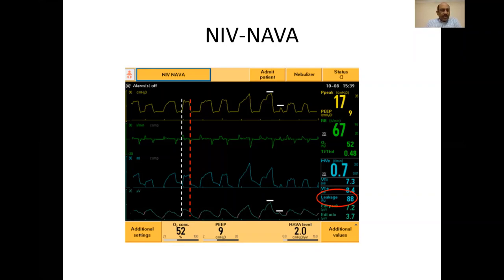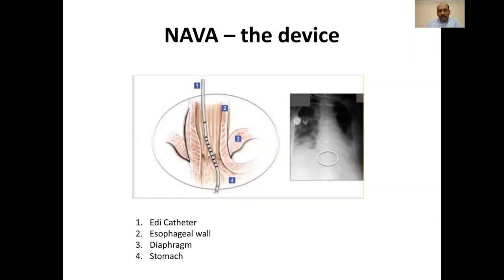By the way, NAVA can also be delivered invasively. The device is an EDI catheter, which is a special feeding tube with electrodes at the end that pick up the electrical signal of the diaphragm. The EDI catheter or NAVA catheter is inserted exactly like any feeding tube, and the position is further refined using the ECG on the screen of the ventilator.